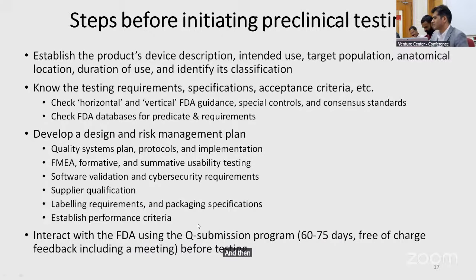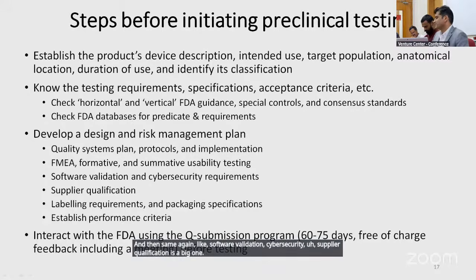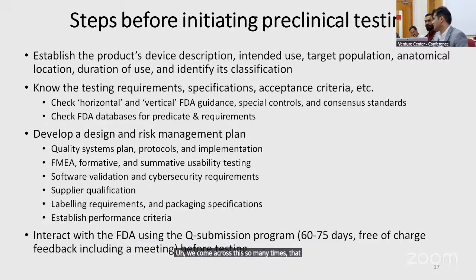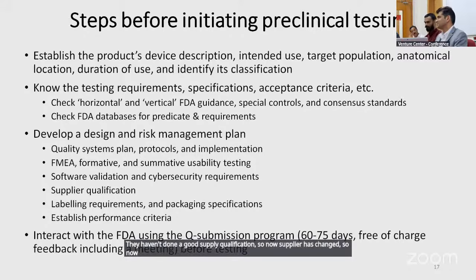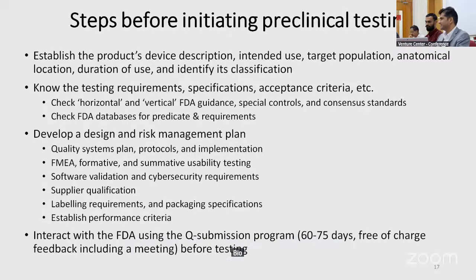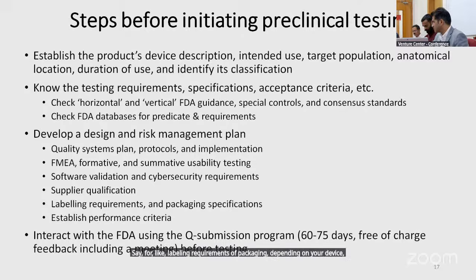And then, again, software validation, cybersecurity, and supplier qualification, which is a big one. We come across this so many times, where they haven't done a good supplier qualification. So now the supplier has changed, so now the chemical composition has changed, which means biocompatibility entirely has to be repeated. So now it's a new submission again. Just missing out on that small detail of supplier qualification could cost you a lot more towards the end. Same for labeling requirements and packaging. Depending on your device, there could be very specific labeling and packaging requirements and performance criteria.